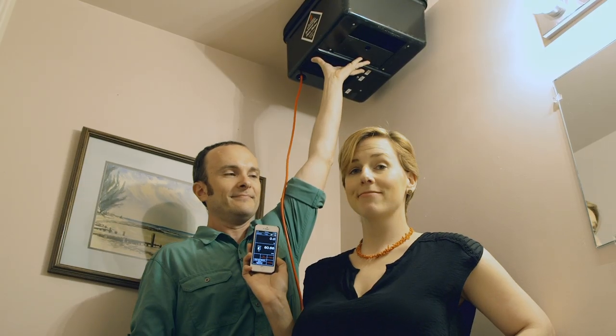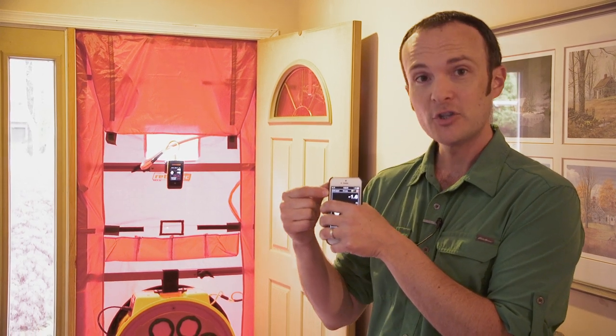When we walked into Matt's house, we immediately identified things that we wanted to test further. And we had fans throughout the house that were trying to deal with different moisture issues. We want to know whether those fans now are pressurizing or depressurizing the house, because all of that imbalance can start to affect the tuning of the home's performance. Now, when we turn on all the exhaust fans in the house with all the doors and windows closed, we went from 0 to -1.5, which is a pretty minimal effect right now before we start changing things in the house. So we want to know where we're starting so that we can know where we want to end up. And we like that minimal effect.